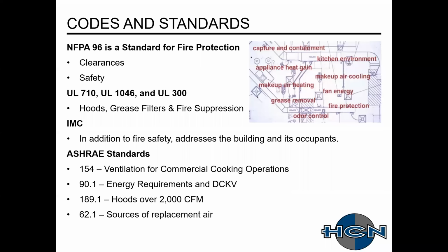The biggest one for kitchen ventilation is clearance to combustibles. UL actually has a test for clearance to combustibles. That's a listed exclusion in 2018, but is not in 2015. So typically that's one of the bigger things that pops up, the clearance to combustibles.